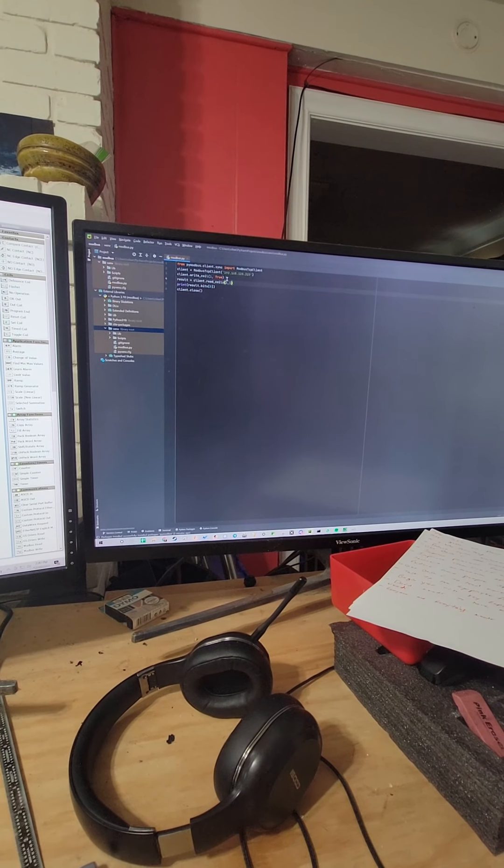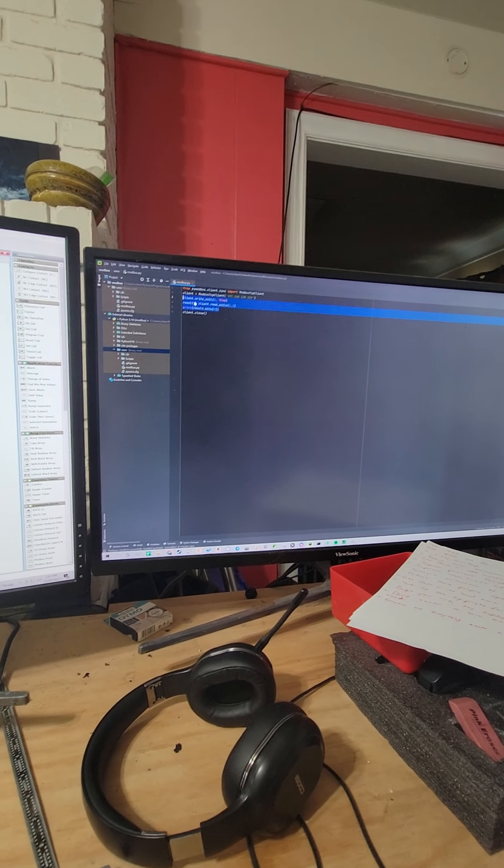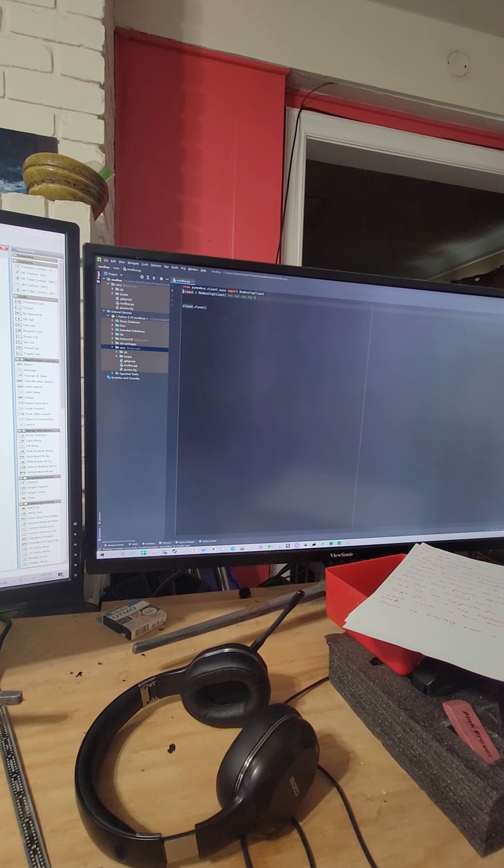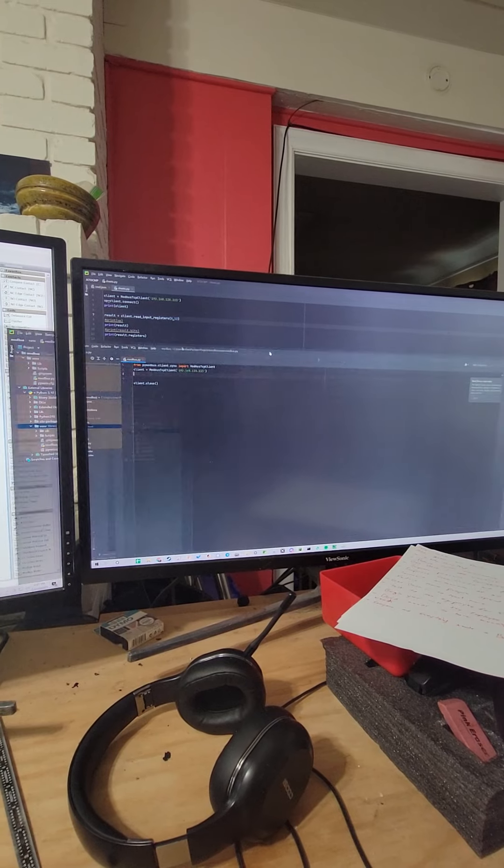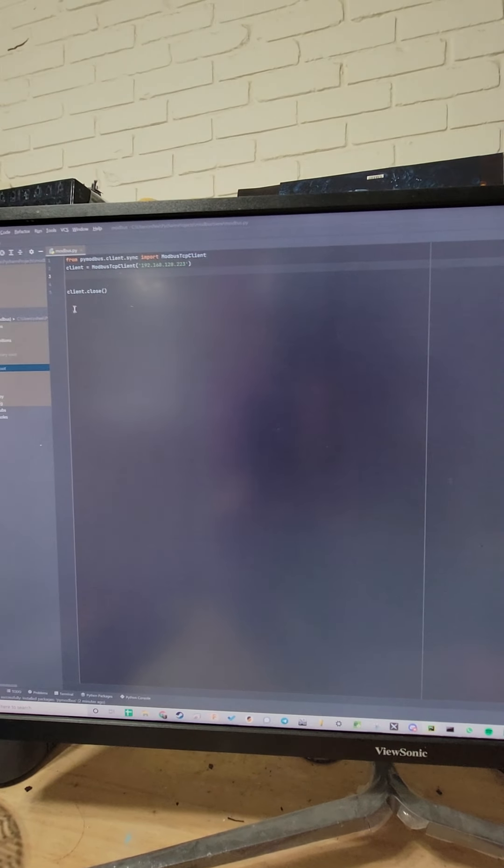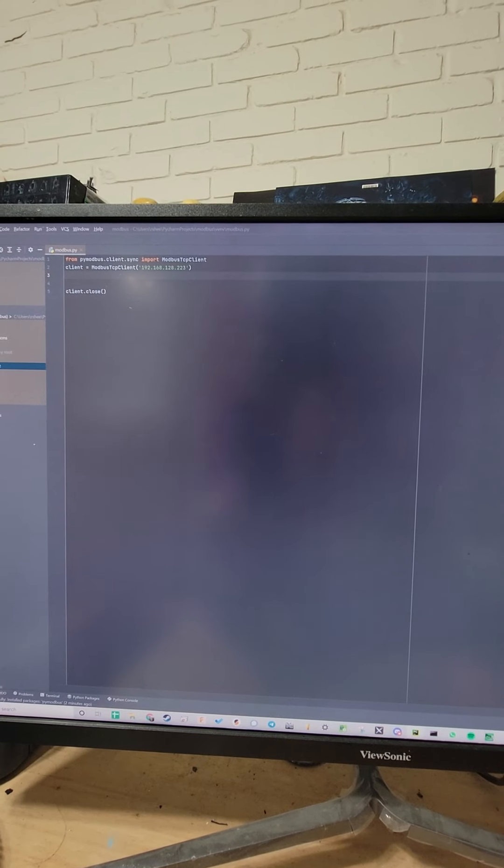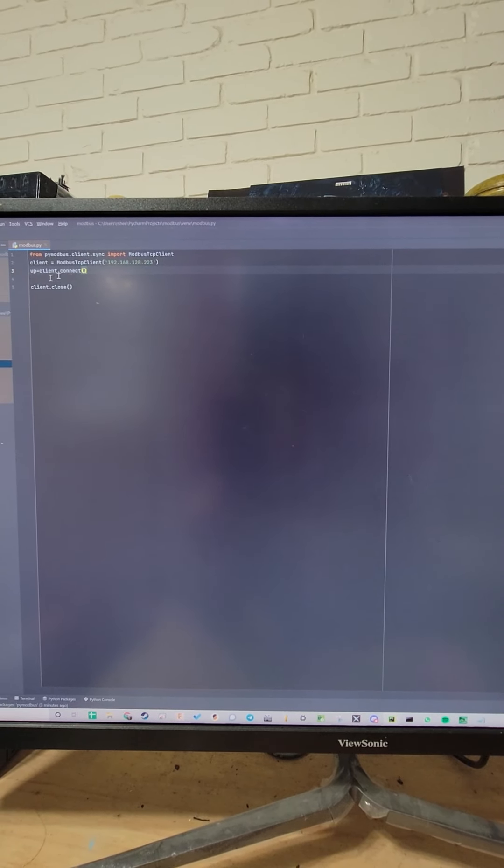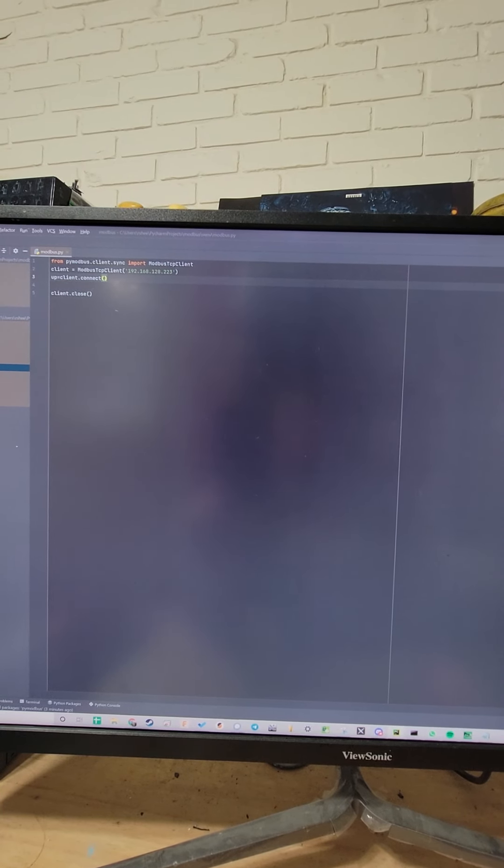Over here, we're going to change our Modbus TCP client to the right IP address. From there, we've got our client defined. What we need to do is we are going to want to connect to the client. We're going to assign a variable as up equals client connect so that we can see the status of it, and then we're going to print that out so we know whether or not we are connected to the PLC.